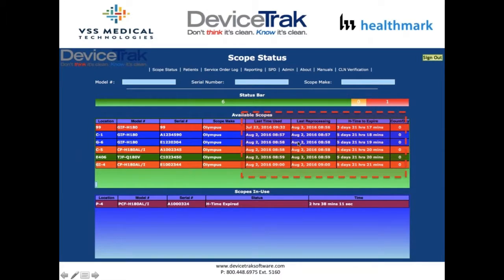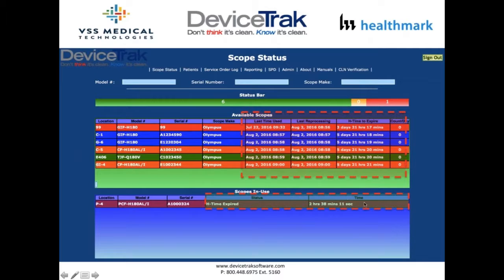DeviceTrak captures the storage time of each endoscope — the last time a scope was used, the last time it was cleaned, and a configured hang time parameter. Once the scope runs out of its parameters, it is moved from the available stage to a must-clean status prior to usage, capturing all time parameters for how long a scope has been stored before needing to be cleaned again.